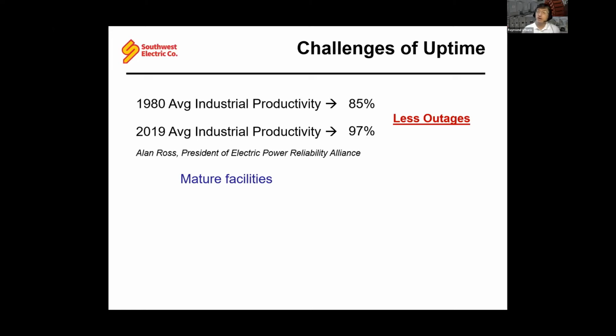So it's very limited in what you can do during that outage time. On top of that challenge of having less time to actually perform maintenance, you've got more and more mature facilities. So you have an aging infrastructure. You have more things that need to be addressed or replaced, and you have less time to do it. In addition to this, we have much more awareness of arc flash safety. And so therefore, before where people would cheat and start working on equipment while energized, well, we have a better understanding not to do that. Or at least if you're going to do that, you're going to be suited up and you are going to be limited in what you can actually accomplish.